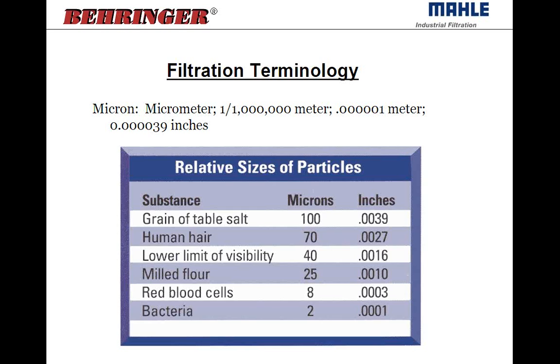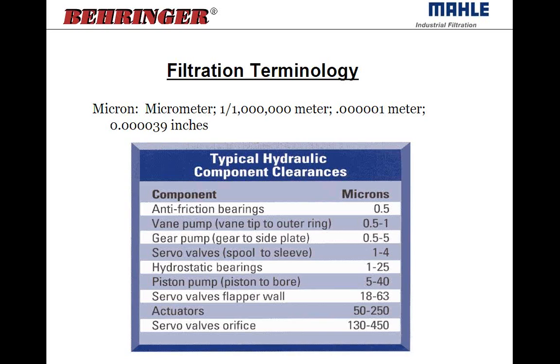Why we're concerned about the micron rating and why we have to filter so fine is due to the type of components used in hydraulic systems and the clearances between individual components. A typical servo valve is one to four microns in the spool to sleeve clearance. We're trying to reduce the amount of contaminants that can get lodged in there or create more abrasion and break down more particles. A lot of the highly dirt sensitive components — piston pumps, gear pumps, vane pumps — are very susceptible to dirt damage. So we're really trying to protect the more expensive equipment in the hydraulic system.